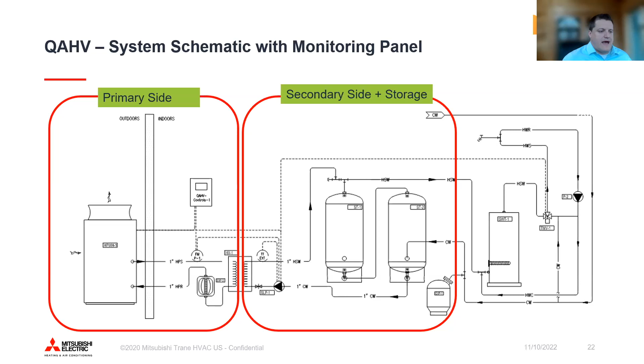And then next is going to be our secondary side, and this is really where our storage is. So we have basically designed specialized tanks to really take advantage of how we store hot water and make sure that we're getting that coldest water coming back to the heat pump. And basically what we're going to do is just control to make sure that we're hitting 140 plus entering these tanks. And you'll see different scenarios where if there's a demand from the system, the heat pumps will basically send that hot water right out to your mixing valve, essentially. But if you're in a storage mode, it's going to start loading up the storage tanks and filling them backward.